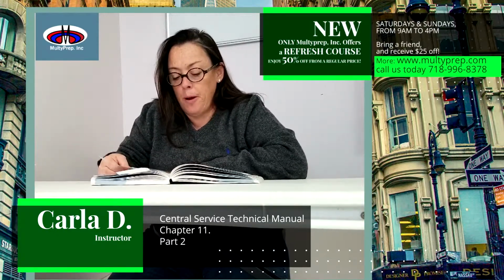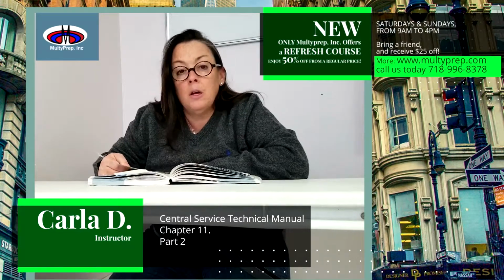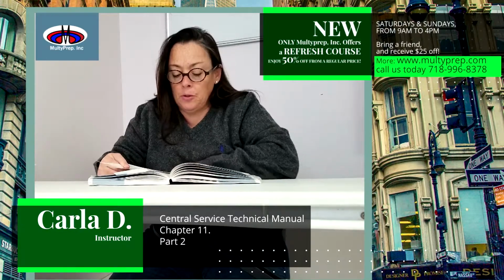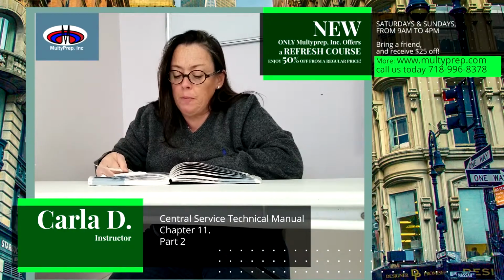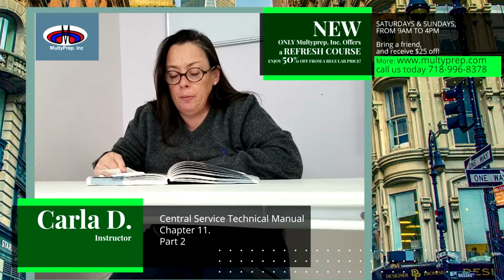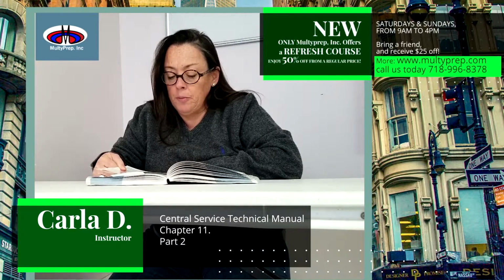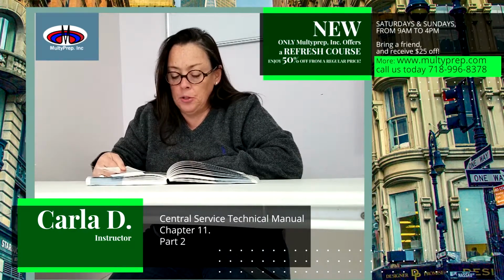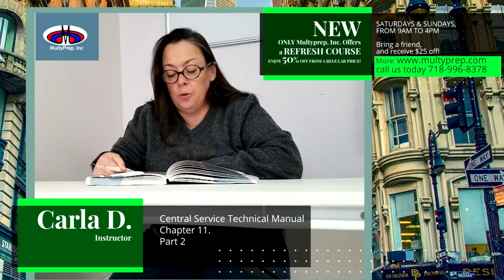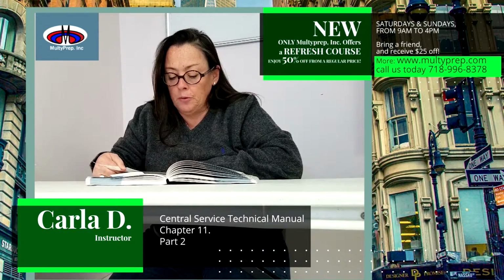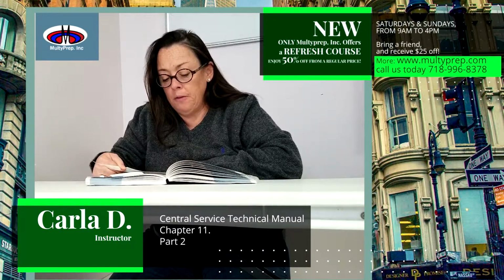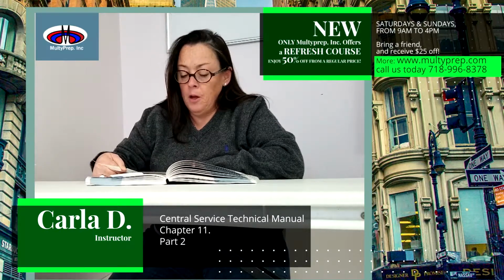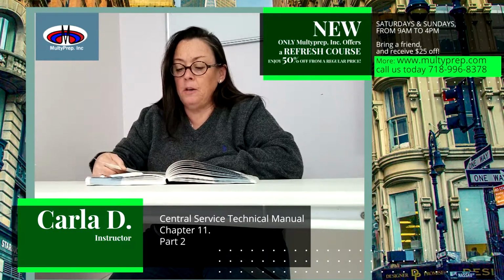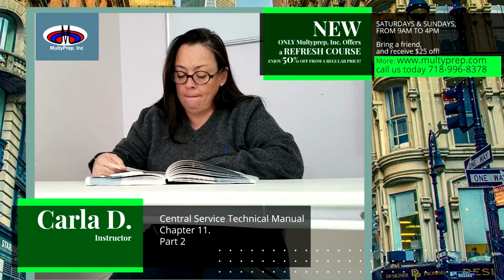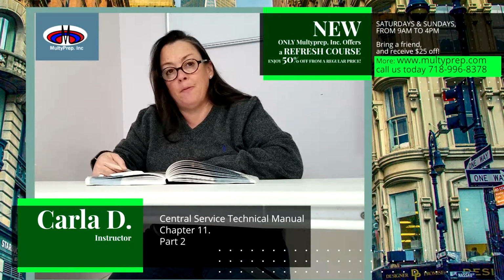Now back over to page 211 to common reasons for powered equipment repairs. Powered surgical equipment is expensive to produce, purchase, and repair. Everyone who handles this equipment should use caution to prevent damage. Common causes of damage include corrosion of internal components from condensation, steam, fluid invasion, or improper cleaning. Physical damage due to mishandling, see Figure 11.23. Lack of or improper prevention and maintenance.